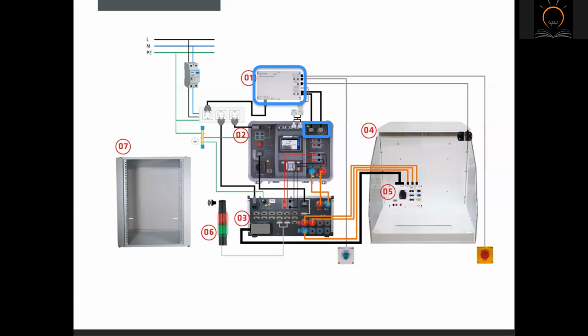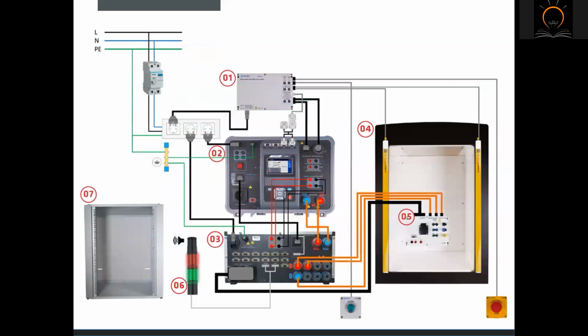The RFID sensor is monitoring the position of the doors. The test sequence can only be started when the doors are securely closed. The cage-closed RFID sensor is coded. Therefore, malfunction or misuse is practically impossible. The next safety system is equipped with a light curtain. The light curtain sensor monitors breaches of the prohibition zone by any object. If the light curtain detects a breach, the safety module will disconnect the measurement circuits from the mains.